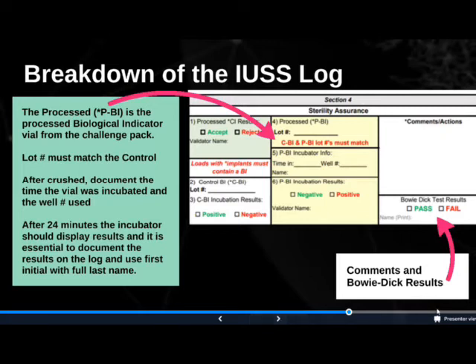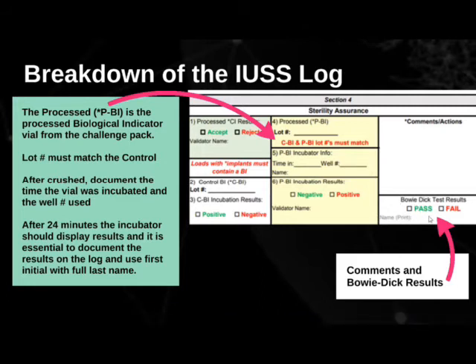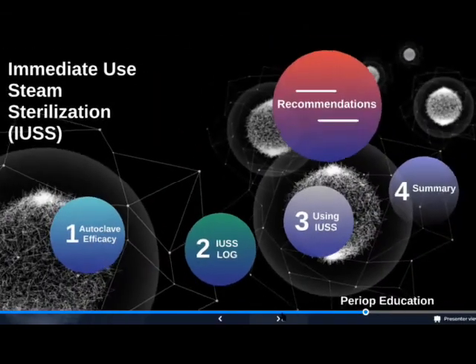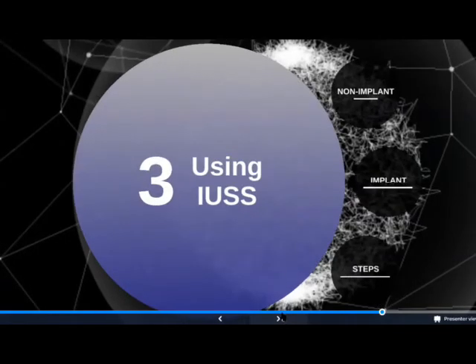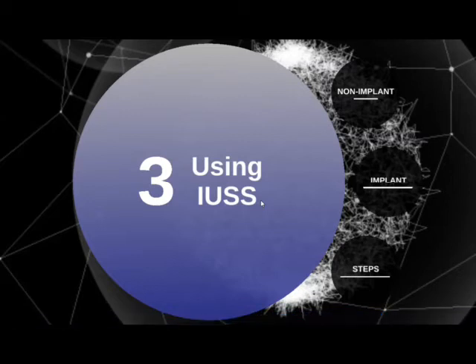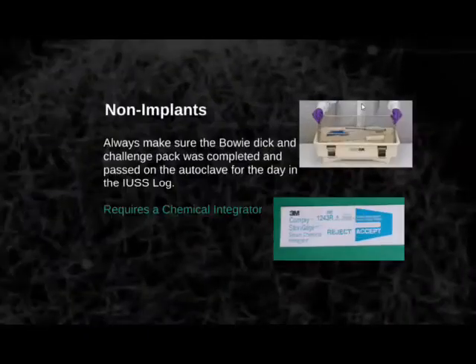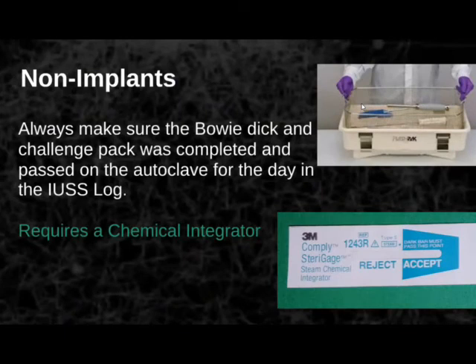All right, so moving forward, on the right side here is where I just wanted to point out that the Bowie-Dick test results will be there. And a lot of times they'll also document the lot numbers, etc. So using the IUSS log, there's two forms that is produced from this. It's either an implant or a non-implant. So a non-implant, of course, that's just potentially an instrument that fell on the floor. Maybe it got contaminated, and this is the only instrument that we have. We have no backups, we have no peel packs, we have nothing else sterile that's going to replace this instrument. So we absolutely have to use it.